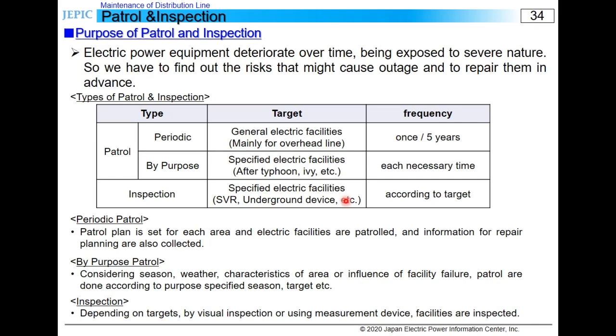The table shows the types of patrol and inspection. The frequency is defined in safety regulations, which are notified to METI. Periodic patrol is done every 5 years. In periodic patrol, all the distribution equipment of each electric pole, mainly overhead lines, is visually inspected every 5 years. The deterioration state is classified according to its degree.